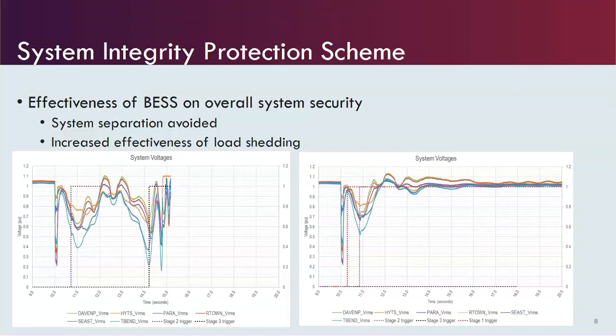If the power flow is still too high, we shed some load as well, preemptively shedding about 200 megawatts of load in South Australia. And the combination of those two things under many circumstances is sufficient to prevent an overload of the interconnector and to keep the system secure. Here's an example of when those two components work well together. Here's an example of when they don't. Okay, so through this system we can give a bit more peace of mind to reliability and security within South Australia.